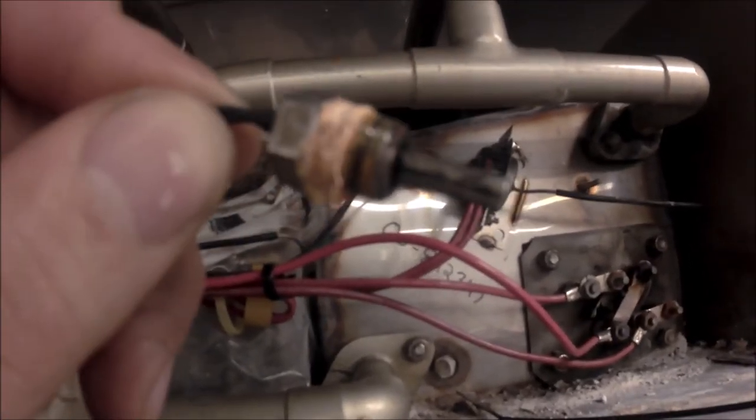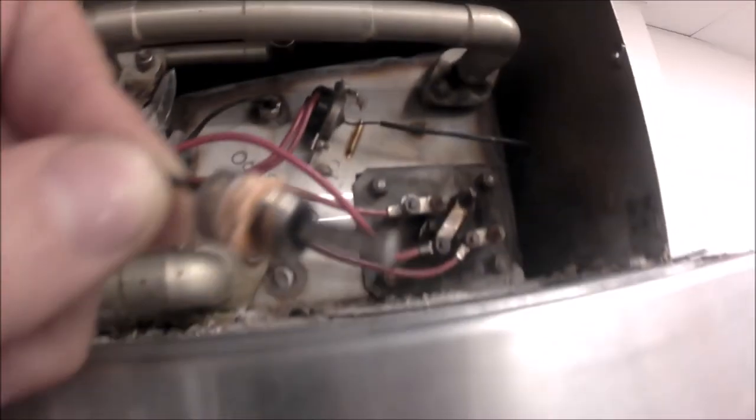First thing I found I had a burnt wire on one of the elements. But the main reason I think is this rinse probe. So let's get that changed out and let's see if that gets us back into our 180 range and we're not overshooting the temperature.